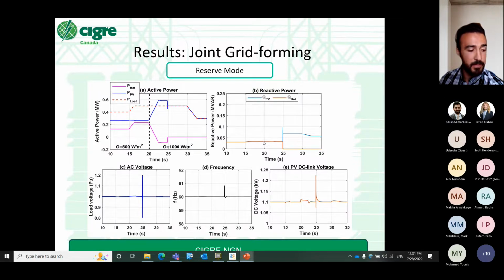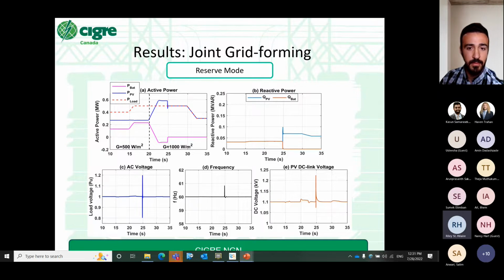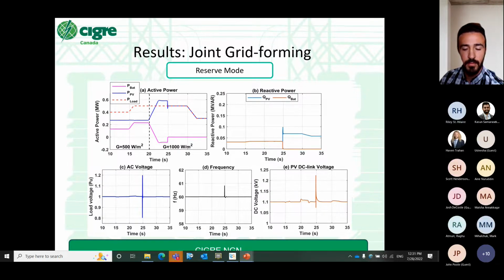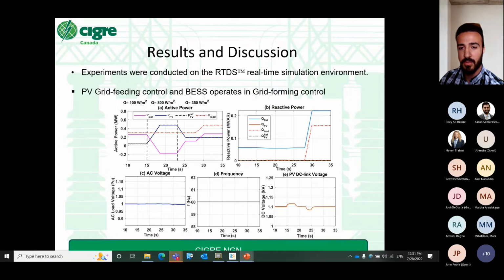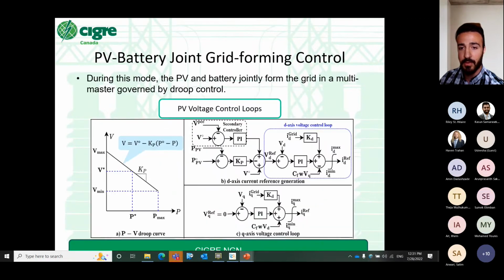I see. Okay, yeah, very interesting. Thank you. Did you find it hard to tune them, to get them stable? No, not really, because these are just droop curves. And if you have your outer voltage control loops and inner current control loops properly tuned, which is almost the case, you won't have any issues. But this secondary controller has to be very slow, because if it is very fast, it's going to override what the droop control is doing. Yeah. So you need.